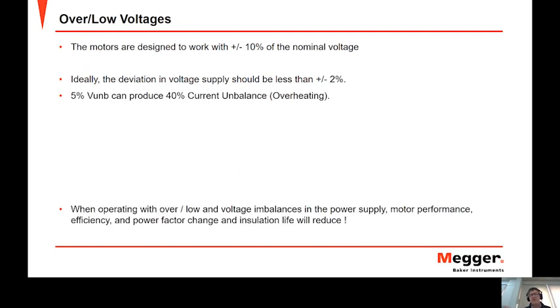And operating with over voltage or under voltage and/or voltage unbalance, then we see the effect in the power supply, the motor performance, the efficiency, but also the temperature within the motor. It will induce higher temperature in the motor, and that will reduce the insulation life of the machine. So this really relates to reliability. We need to be sure that our power supply, our power quality being fed into the motor, is of the right level and balance to avoid overloading our motor thermally.